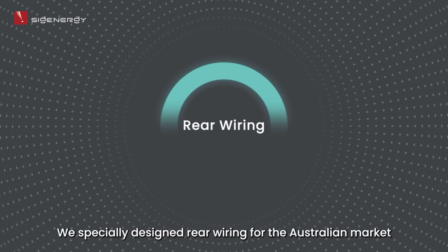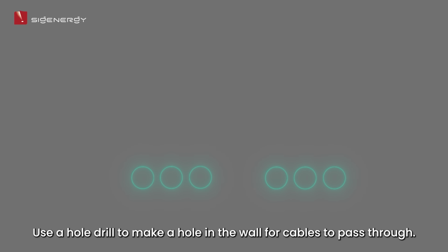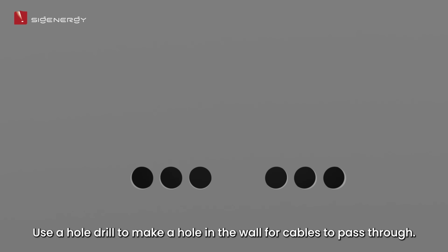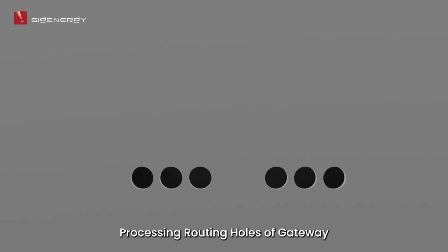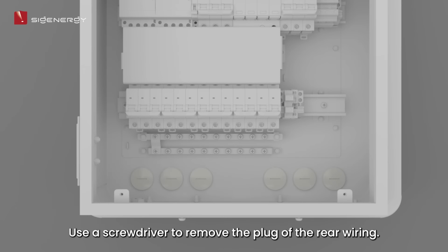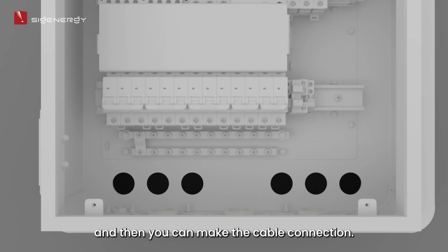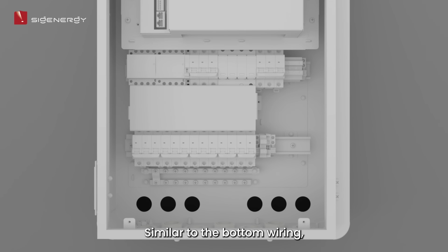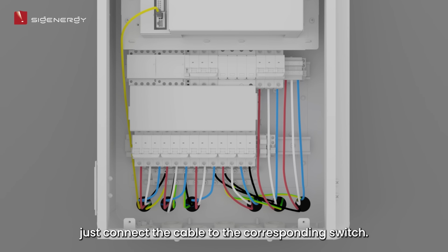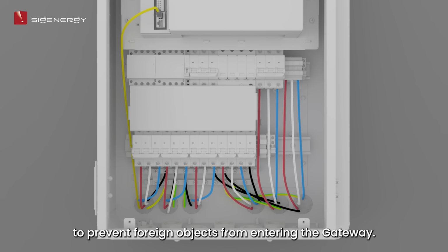We specially designed rear wiring for the Australian market. Use a hole drill to make a hole in the wall for cables to pass through. Processing routing holes of gateway. Use a screwdriver to remove the plug of the rear wiring. Pass the cable through from the back, and then you can make the cable connection. Similar to the bottom wiring, just connect the cable to the corresponding switch. Finally, seal each opening with fireproof putty to prevent foreign objects from entering the gateway.